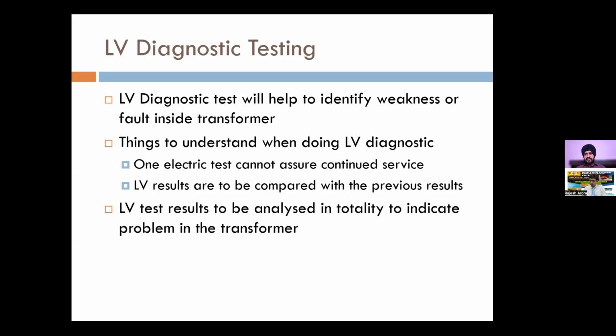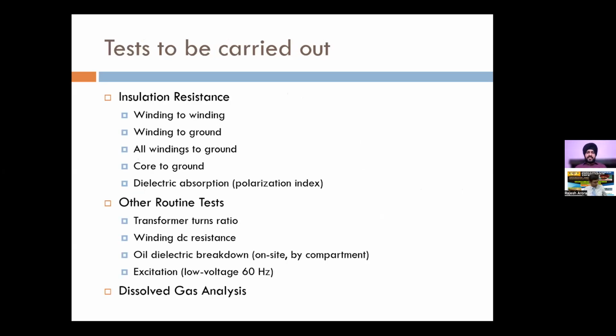If there is definitely some fault, you will need to go to the next step, which is the internal inspection. But the LV tests may give you an indication of the likely fault inside your transformer, and would give you some assistance in making the final decision. So all these LV test results are to be analyzed in totality to indicate what the problem in the transformer is. So what are the tests?